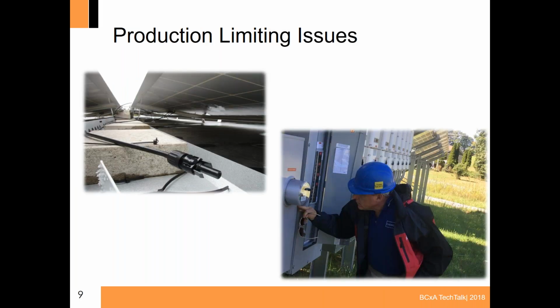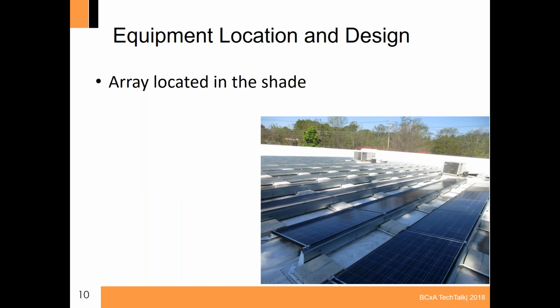So now we'll just touch upon some issues that would limit production. Again, we touched upon these already, but we'll give you some visuals here. The most common one that we would see limiting production, but really the least common on a well-designed system, is going to be array shading. Sometimes it's obvious, like this photo here, where it appears to be in the middle of a sunny day, and we see that half of this array is in shade. Shade drastically reduces the production. And like I had mentioned, even shade on one or two modules, you'll lose the whole string. So if each string is, say, 3 kilowatts, you lose one or two modules, that whole string will go down.